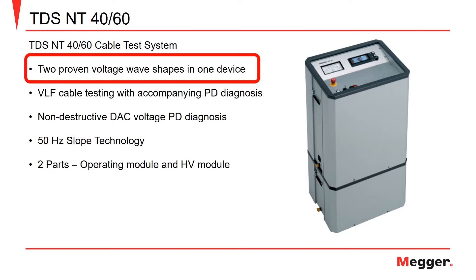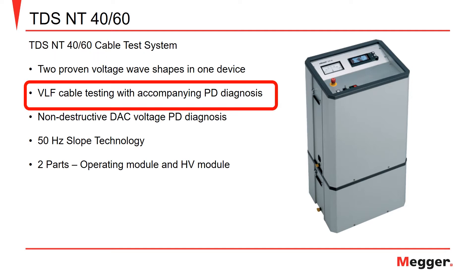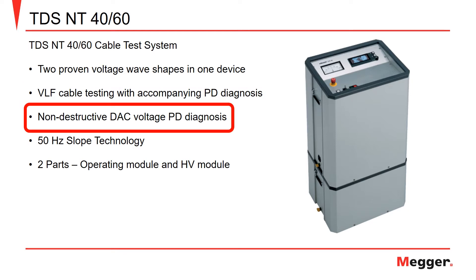The Megger TDSNT has the ability to test with two proven wave shapes in just one device. These are the cosine rectangular or damped AC waveforms. The TDSNT can be used to perform VLF cable testing and partial discharge measurements. The standard compliant VLF cable test uses the cosine rectangular waveform, while damped alternating current voltage is applied for partial discharge testing.